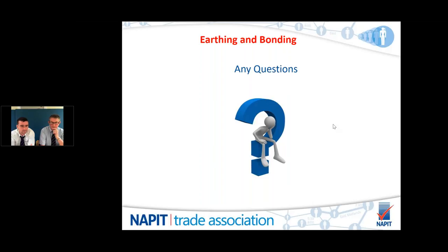So we've just got a couple more. One from Neil, who's asking, on a central heating system, some of the time the plumbers use copper tails through the walls for taps or for radiators. Where does this come in requirement for bonding? If there is no bond on the water due to it being plastic and the boiler pipework is all plastic? The parts go through the wall. No requirement. It's not an exposed conductive part. It's not an extraneous conductive part. It's got no chance of becoming live and therefore doesn't need bonding.